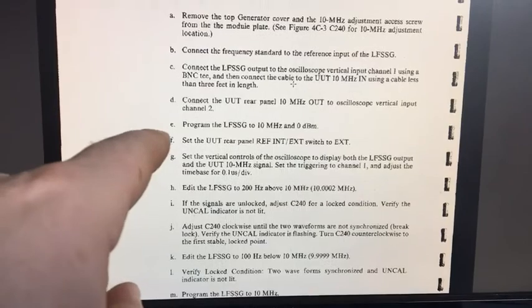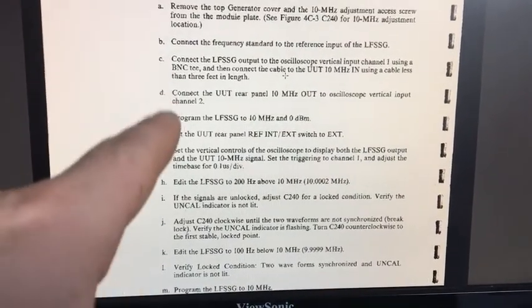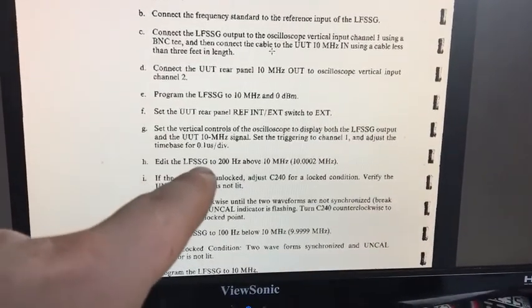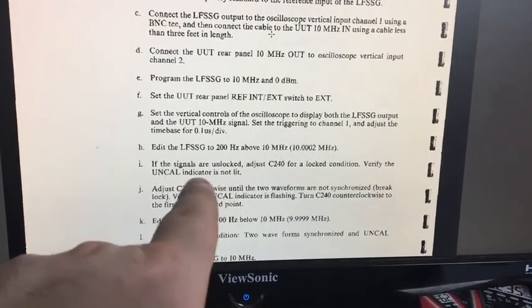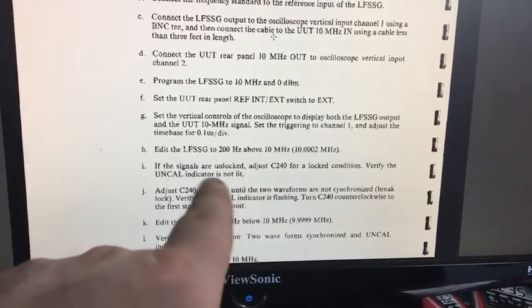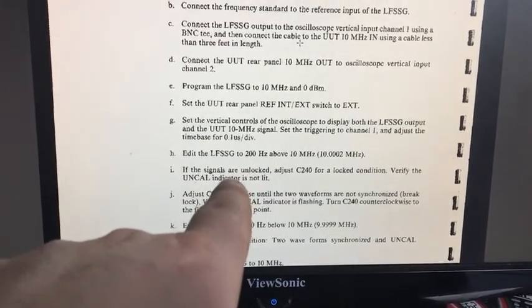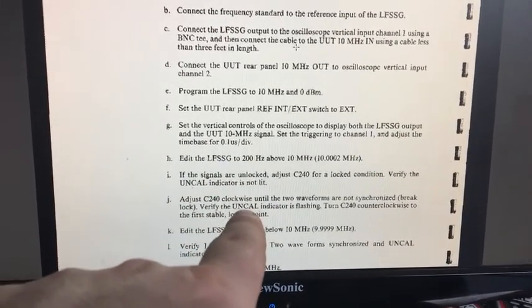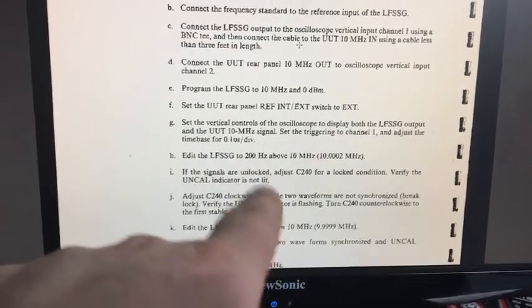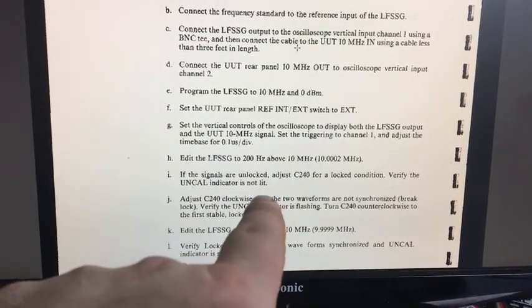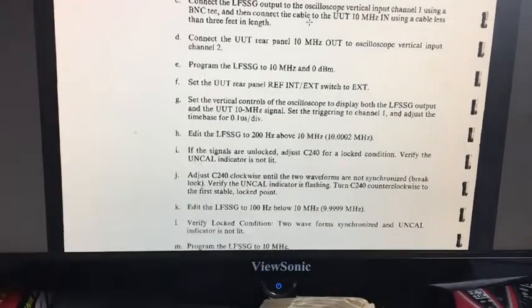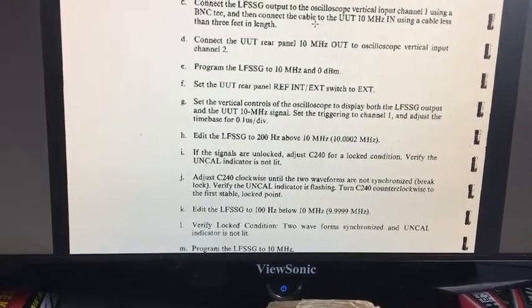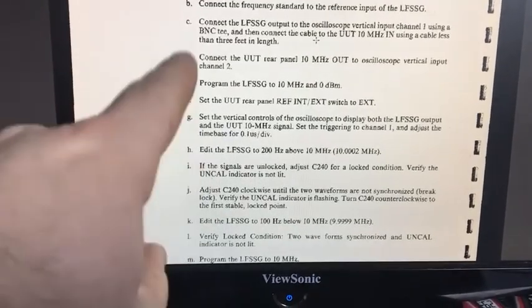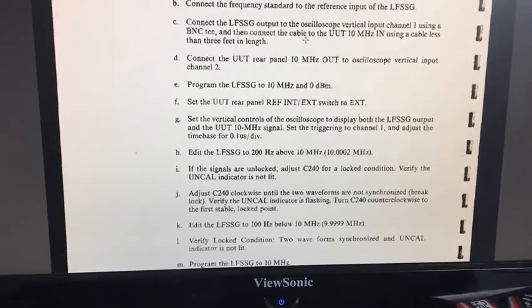I'm going through this procedure here. That's okay, but it mentions about the signals being locked, right? So you're viewing the two waveforms, and it should lock together, so they're in the same frequency domain, or at least matching frequencies. But that's not actually happening. I'm doing this adjustment. The adjustment itself is working, but if I adjust, it's not working. So it looks like this PLL section here isn't actually adjusting.